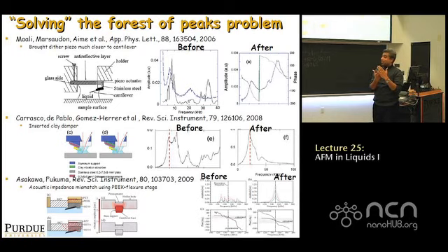That's one option. If you bring the piezo close to the cantilever, as close as possible, you reduce the number of structures that can resonate, right? If you keep it very far away, then you shake more things in between, right? So try to get the piezo as close as possible to the cantilever.